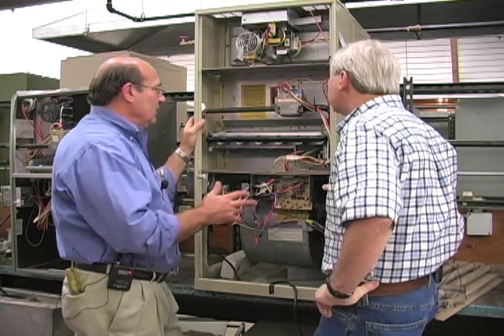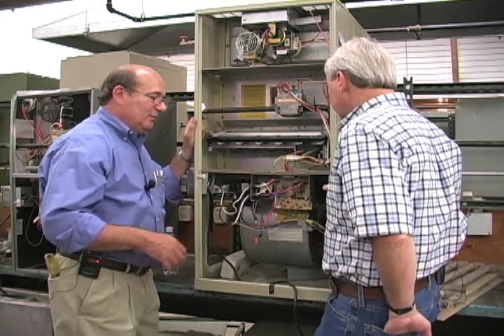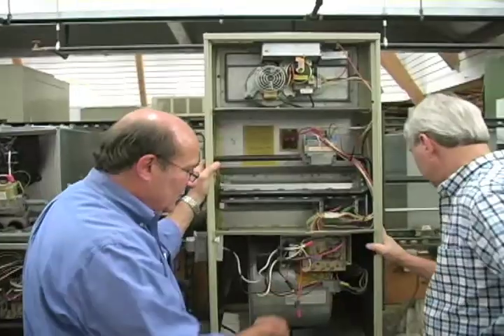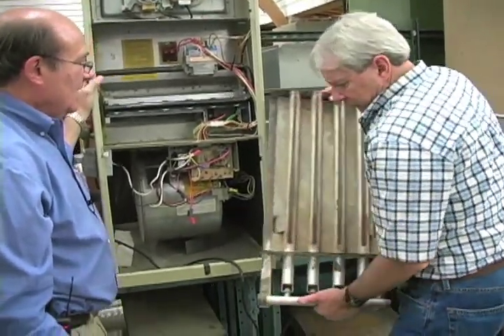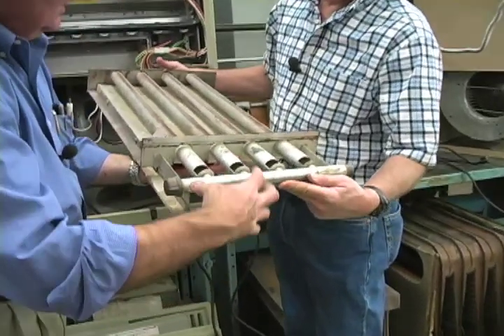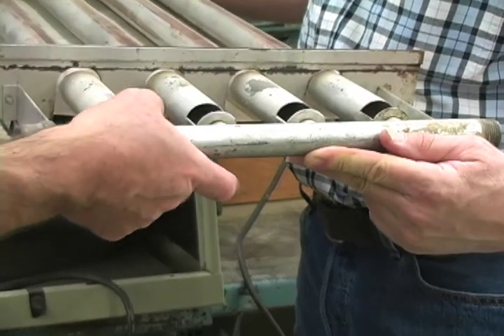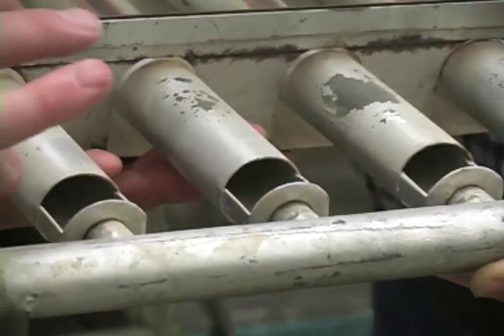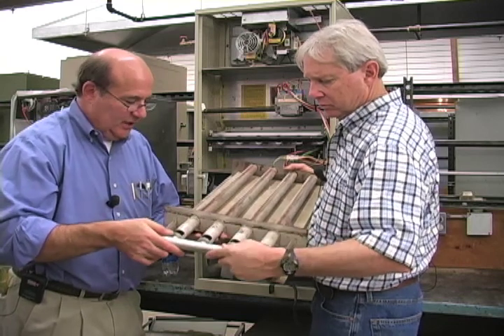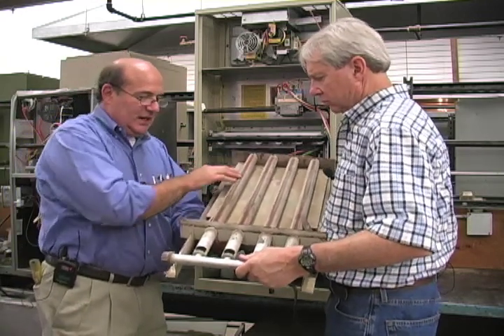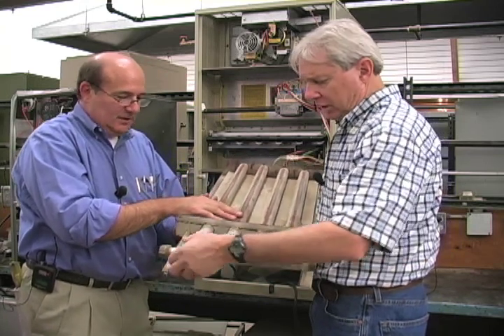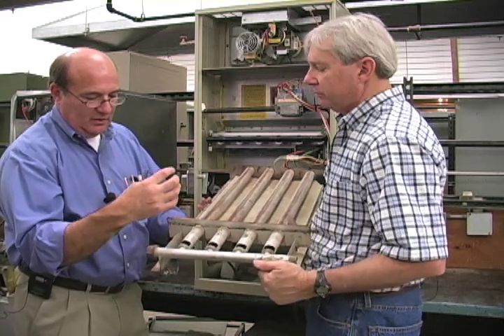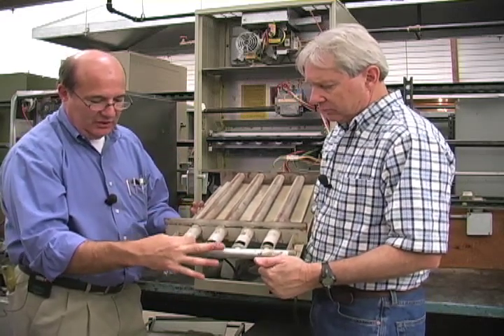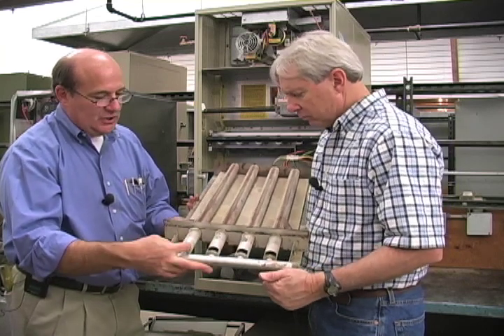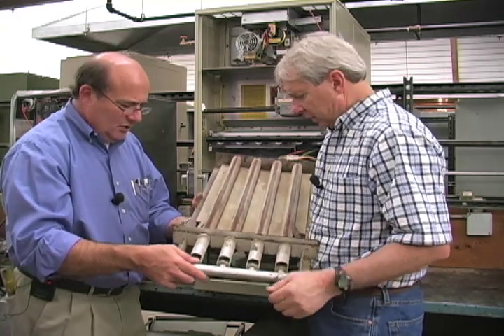One other thing that's a little bit different on this furnace is this type of burner that we have. On the old 65%, we had the old-fashioned ribbon type burners, and there's a rack of ribbons right behind you there. I can show you that. On the one that we had just looked at before, we had big air adjusters on the front. This one has air adjusters over here. They're all missing here, but it's a kind of a cylinder that goes around here, and you can rotate it through an opening and bring the air in through the different burner orifices at this location. Then the gas is injected here, and the flame rides on this ribbon type burner over here. So the adjustment would partially cover this opening right here. It's like a little cylinder with two holes in it, and you can rotate it so that the holes are either blocked off by this or they're rotated around, and you can adjust the individual burners with those. It's an old-fashioned ribbon burner.